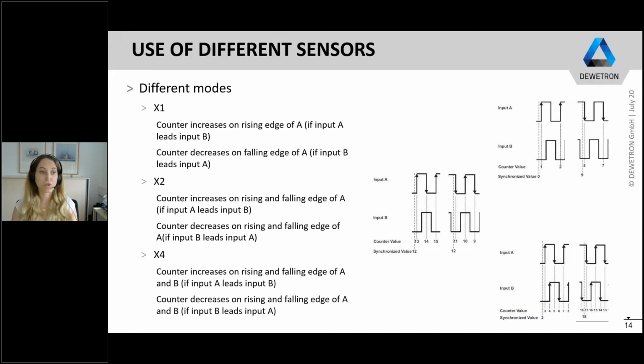So here it's just important which input leads the other. For X4, the rising and falling edges of inputs A and B are counted. And here it also is important if input A leads input B or input B leads input A. So if you want to use a special mode, you should also make sure that the hardware supports this mode you would like to use.